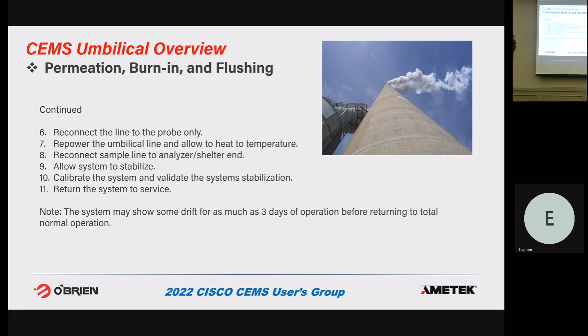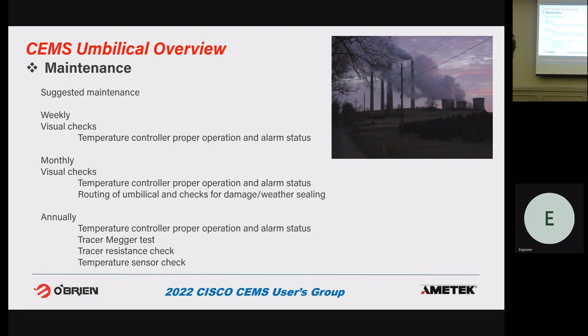All right, so these are our recommendations: visual checks done weekly, and it doesn't have to be an intense hour-long check. If it's a stack, just look up the stack to make sure it's not sagging or falling off. We've had customers report that after installation the pipe clamps in the Unistrut walked out, with 2 or 3 clamps hanging loose. So our recommendation became adding little angle pieces on either side so it can't walk out of the Unistrut. Since we recommended that years ago, I haven't heard of it happening again. So just do a weekly visual check and check the temperature controller for alarms. Monthly, do the same visual and temperature controller checks plus check the routing of the umbilical. Annually, do megohm and resistance checks.